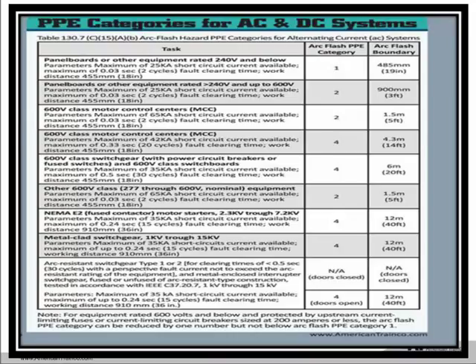And we'll see in a slide coming up, if the arc flash boundary is in excess of the limited approach boundary, that would be where we would put up our barricades or tapes or cones to keep the unqualified people away. So this table is going to be used in conjunction with the previous table. If we answered yes on that previous table, that we do need arc flash PPE clothing, then we are going to have to come to this table, and it would tell us what level of clothing we're going to be under for a particular type of equipment that we do approach. So you can see 480 volt equipment, the arc flash PPE category is going to go to a 2, and my arc flash boundary would go to 3 feet.